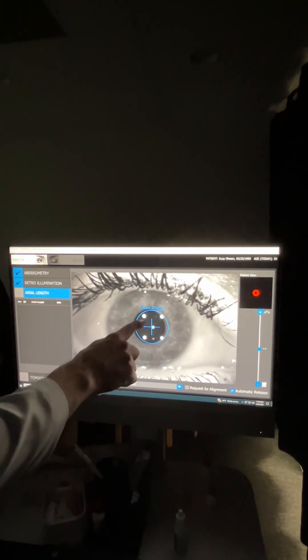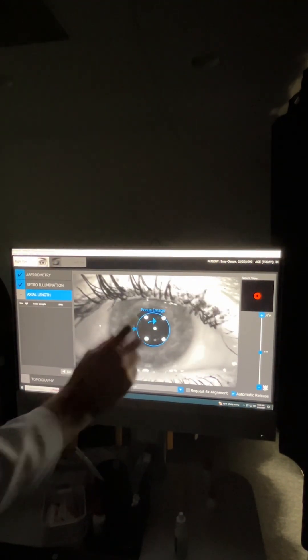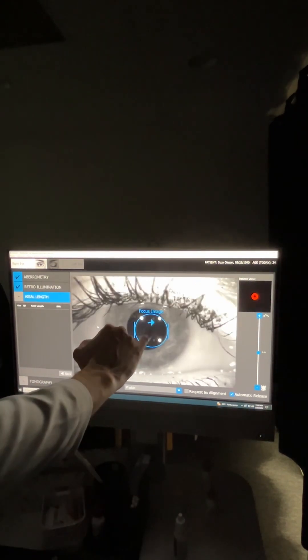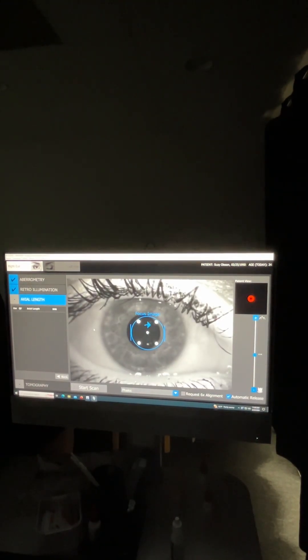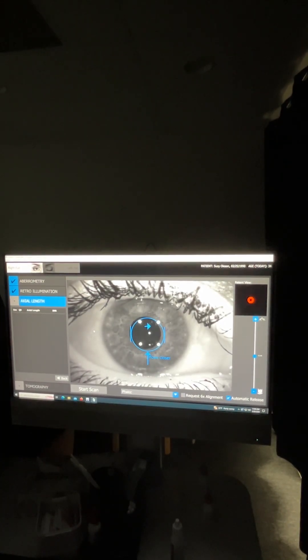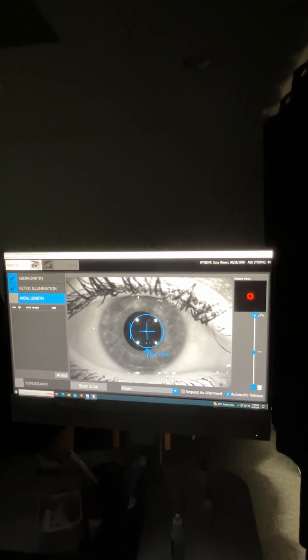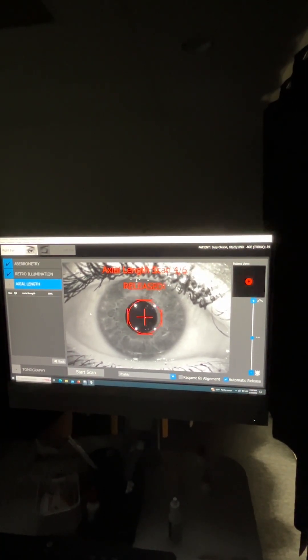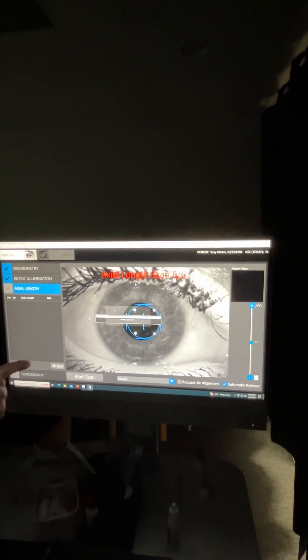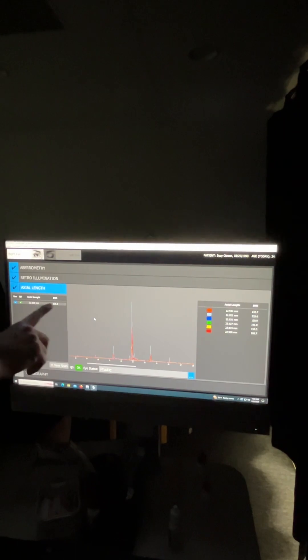Otherwise it's much the same. You're going to have a blue circle and you want the little white dots to get small and in focus. And then when this little cross here in the middle is also in line with the circle that's flashing, then it's going to capture six ultrasounds, six A-scan ultrasounds or optical biometry ultrasounds. So try to keep the cross right on that central one, and then it's going to do in consecutive order six ultrasounds. Once it does that, it processes the information and it's going to average out your axial length measurements, which is the length of the eye from front to back. And you can see that information right here.